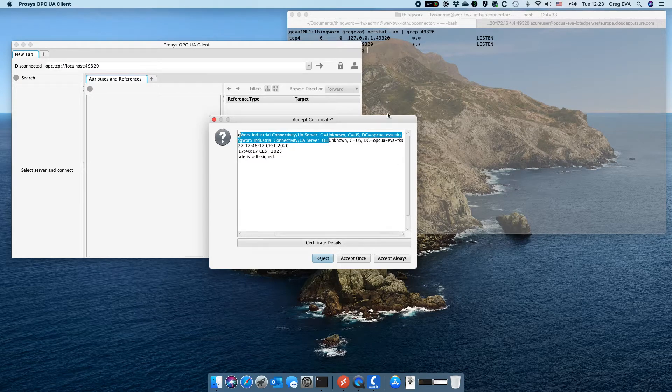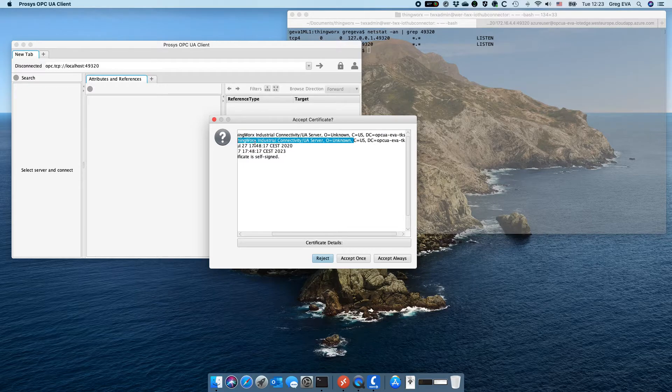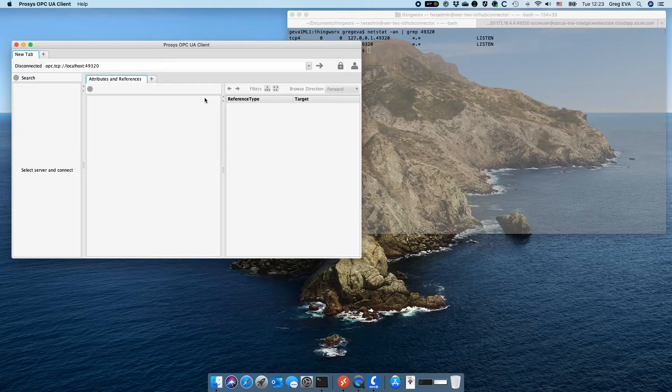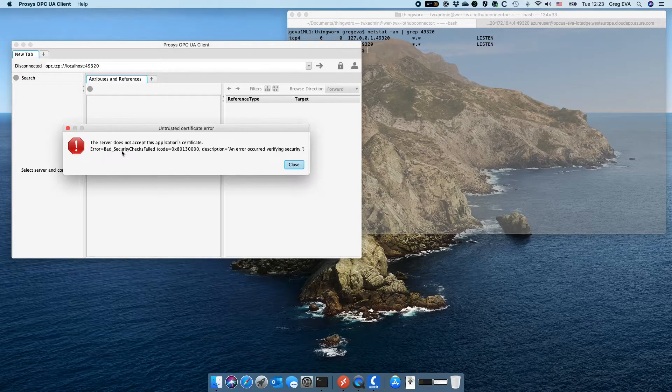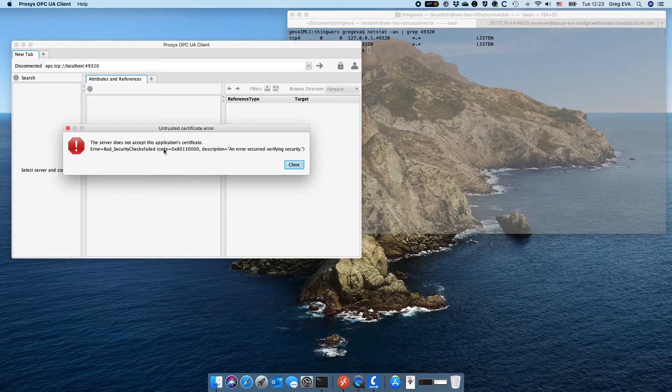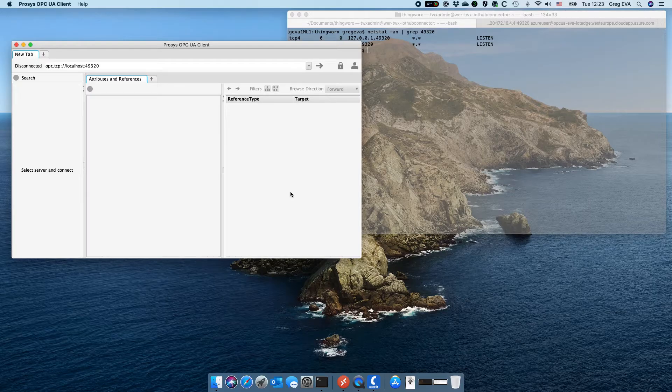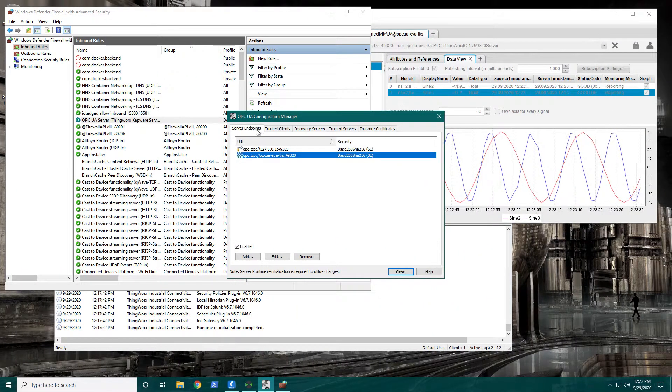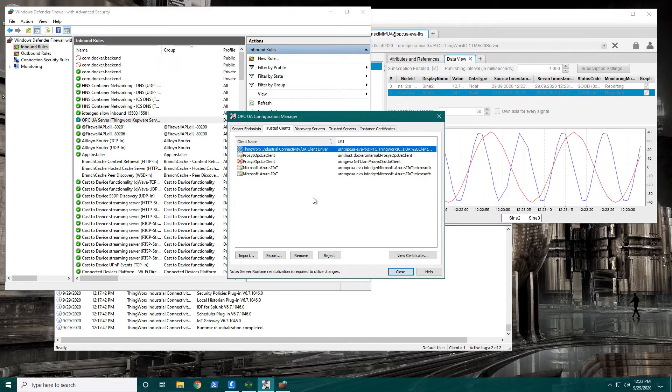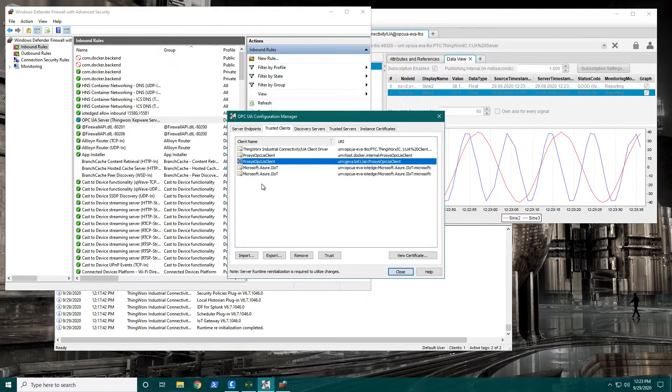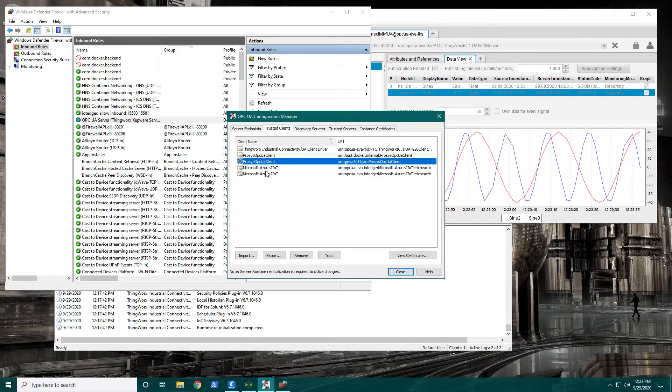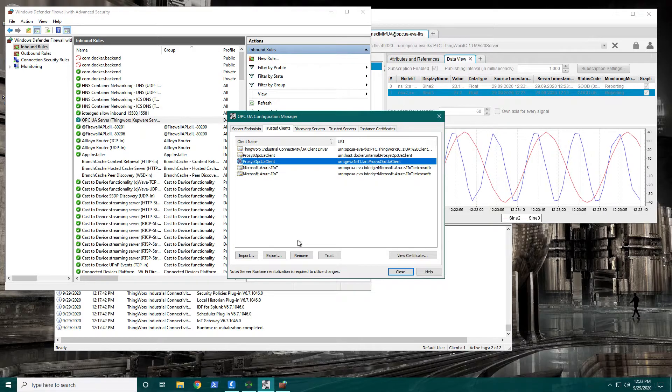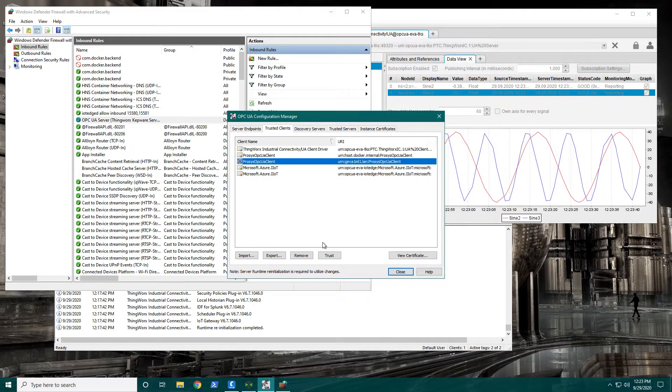Which is great, I can verify that this is the right one and I'm going to accept. However it says that the certificate doesn't accept my, the server doesn't accept my certificate. This is normal Kepware behavior. We're going to come back over to Kepware and we're going to have a look at the trusted clients and we see that there's this ProSys OPC UA client that has been essentially received by Kepware but it's not trusted by default so we need to trust that.